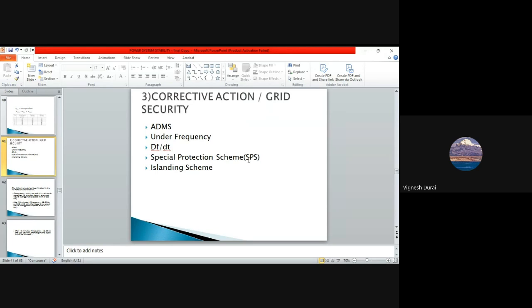Okay, your frequency should be within 49.5 to 50.3. This is mandatory as per IEGC standards. Everything I have discussed will be applicable to your microgrid if you are connecting with the main grid. Okay. Next.